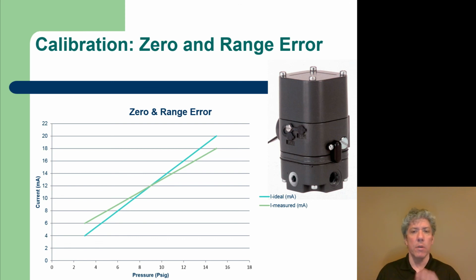So the first thing to do when you're calibrating this sort of thing, the first thing to do is always to adjust the zero first and then the span. The span does affect the zero, but obviously not to the extent that the zero does. So the first thing to do to get that green line to lie on top of the blue line is to adjust the zero, bring the whole curve down, and then increase the span or increase the range. After you do that, it's important to go back and check the 0 point again.